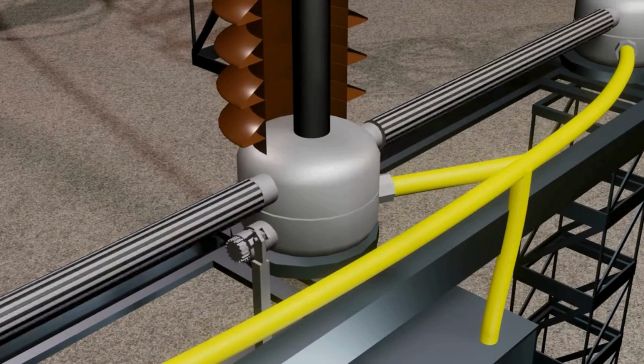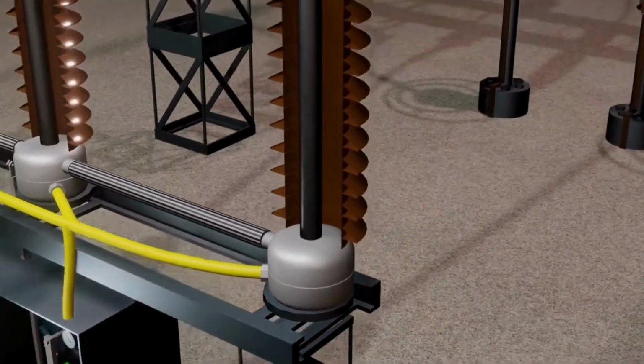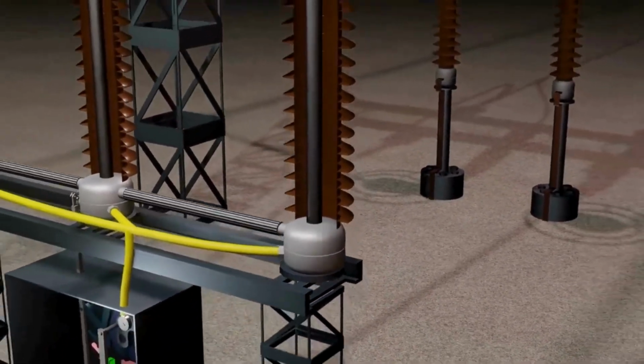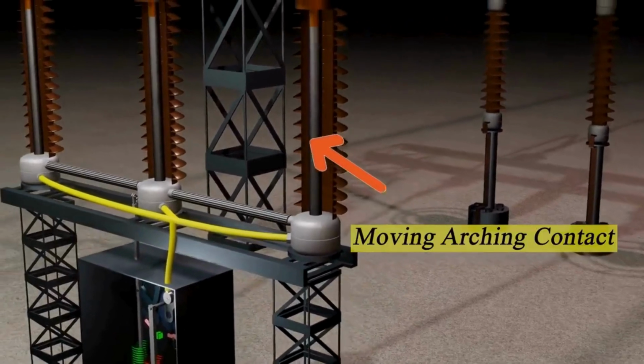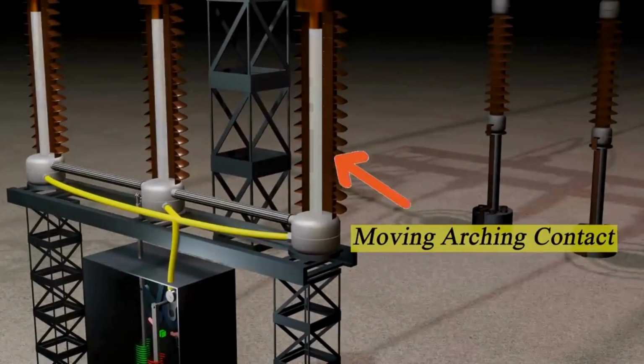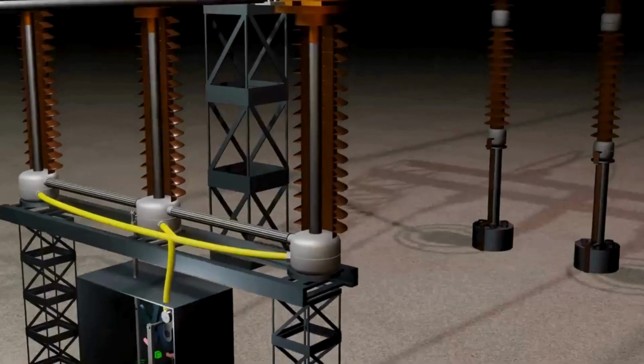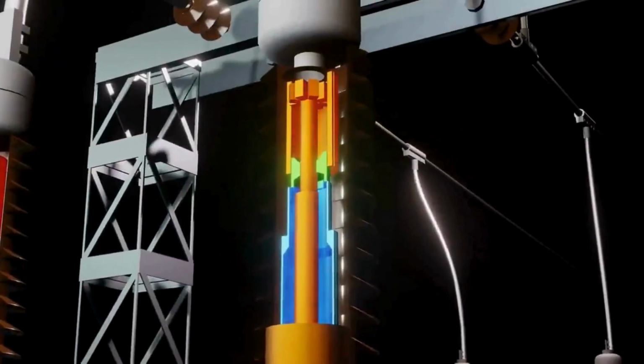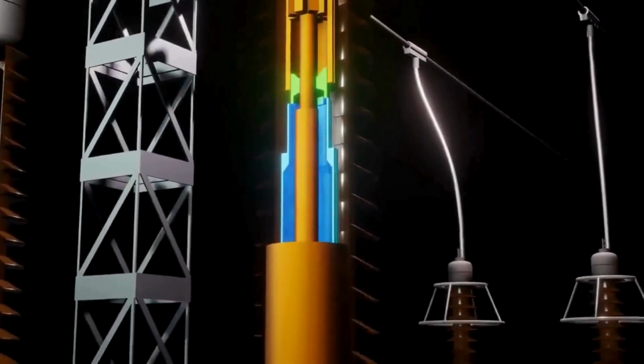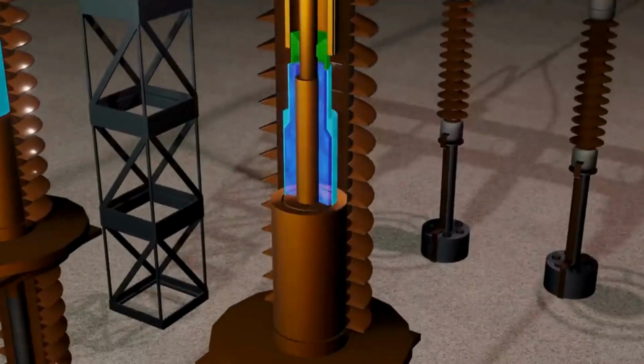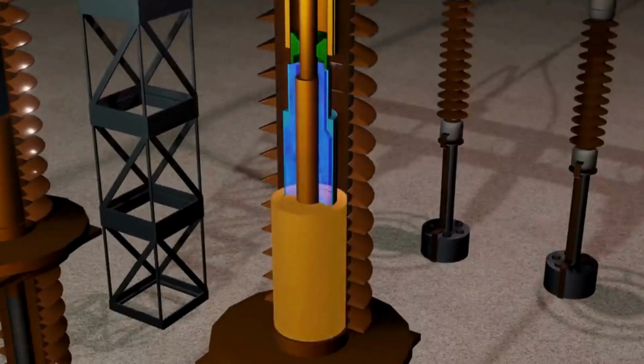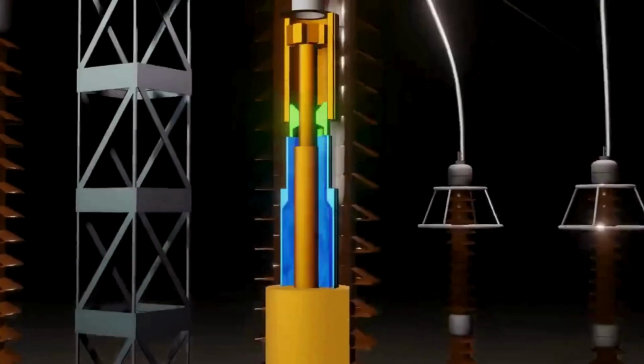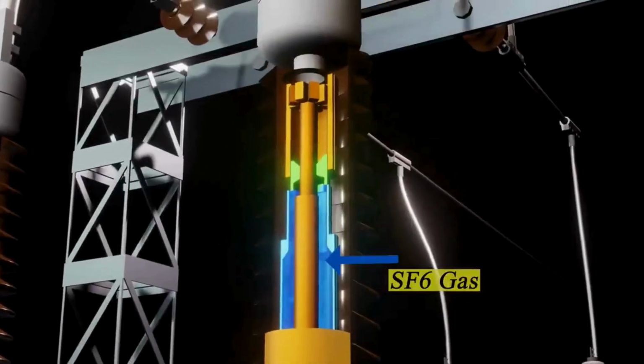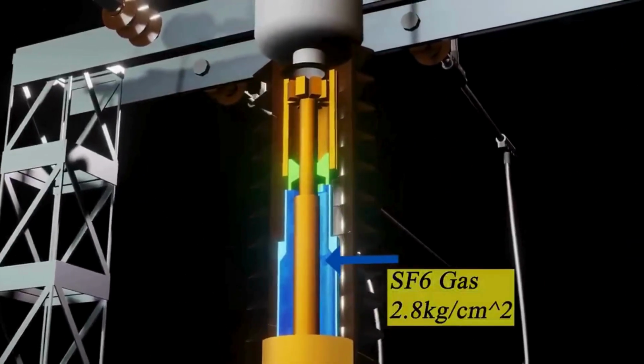This high voltage line did not even leave the isolator, then how will the circuit breaker leave it so easily? When the spring comes down, a small gearbox is installed under the bushing, so that the three bushings are connected to each other and the force of the spring can reach all three bushings equally. When the spring goes down, the force of the spring comes on this rod, which is called the moving arcing contact. This rod is insulated from the bottom and connects with the upper contact from above.